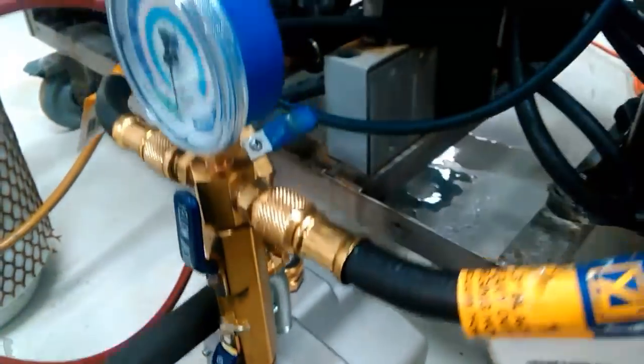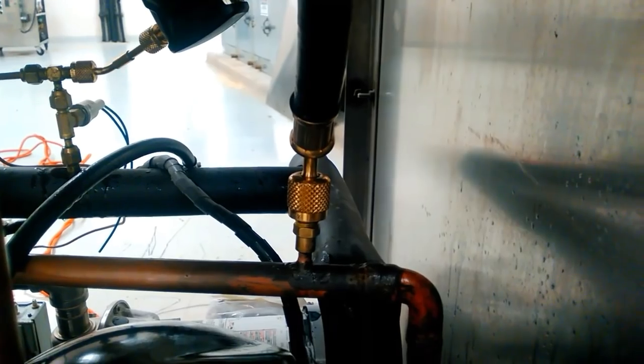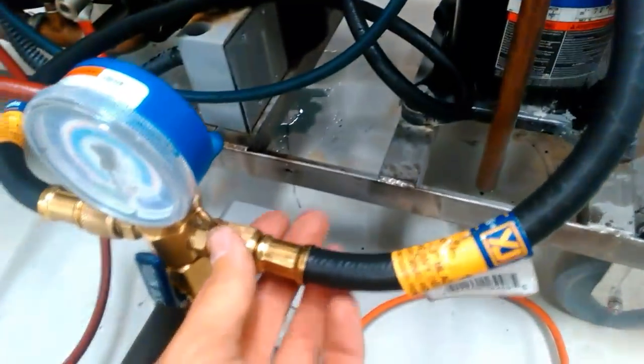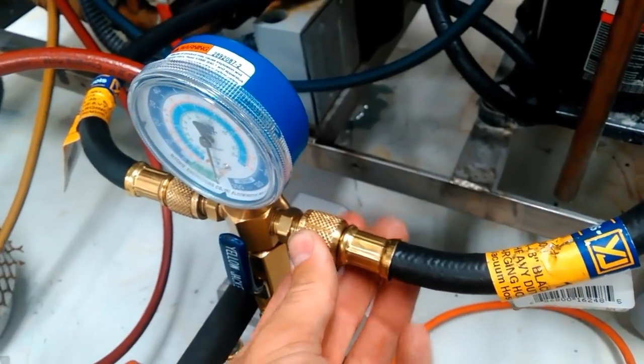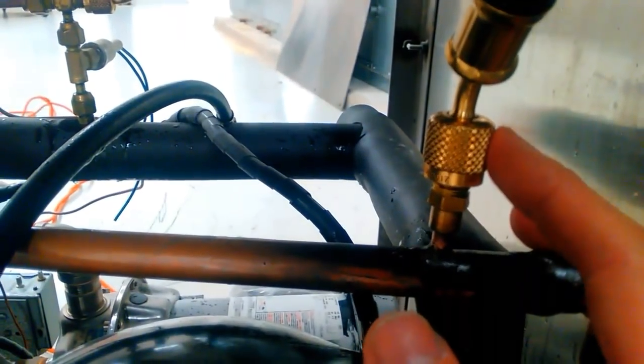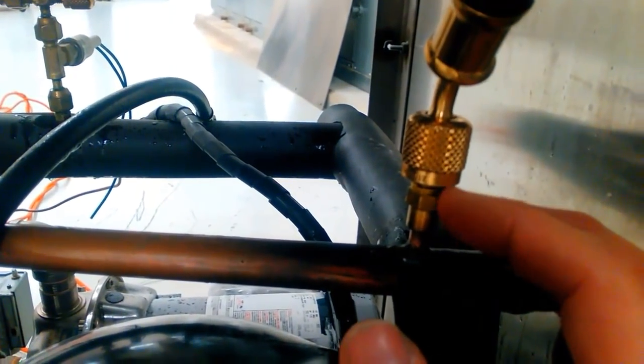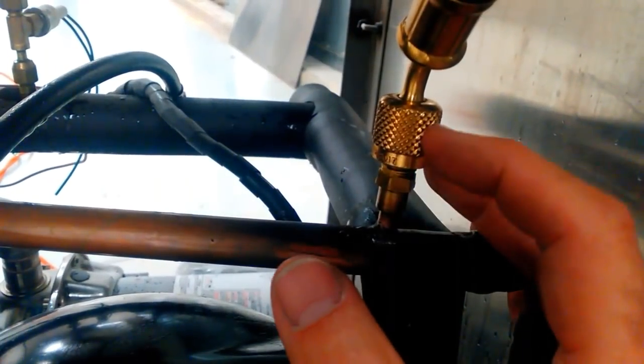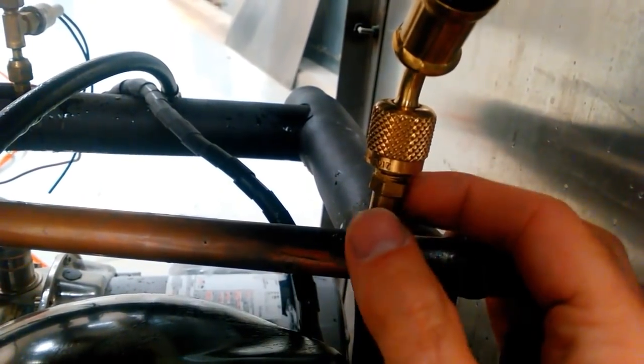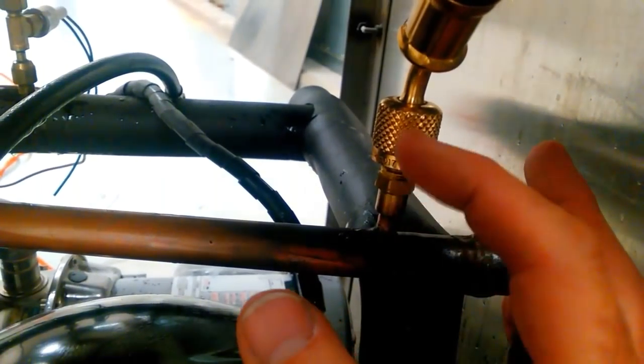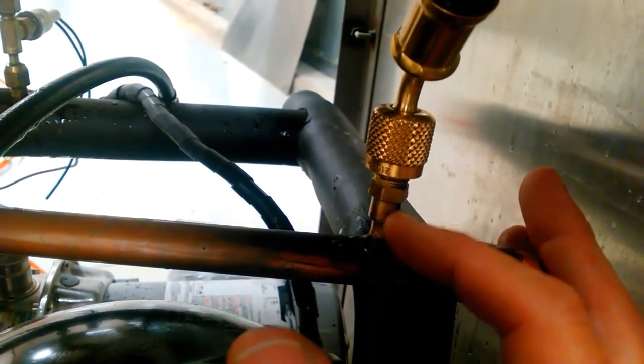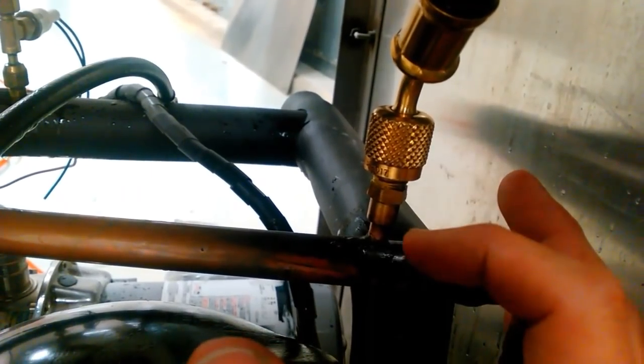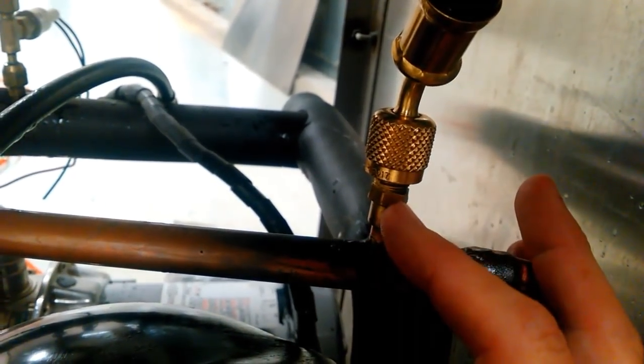So let's start at the system and work our way back. That's the 1/4 inch connection with a vacuum-rated vacuum hose. The 3-8s connection on the other end is for EVAC. Normally what we all should do is remove the Schrader with the Schrader core removal tool. But this Schrader is jammed up in there because somebody mushroomed the fitting and I can't get my core tool in there. We remove that Schrader to remove the restriction. When you remove the restriction, you have more flow. We have to live with it this time, but in the future, let's try to get the Schrader removed.